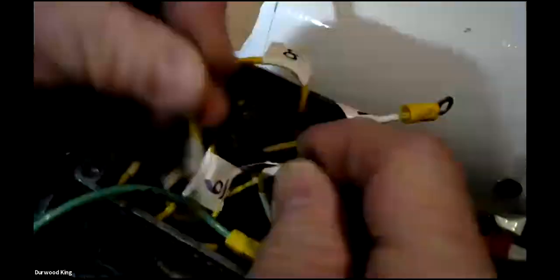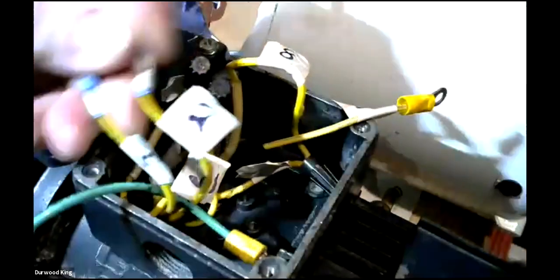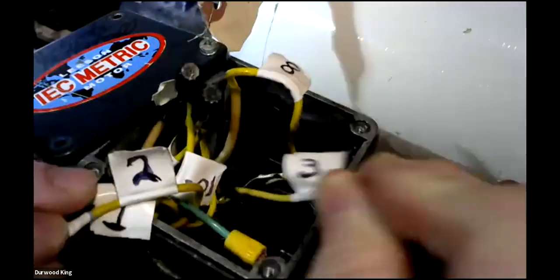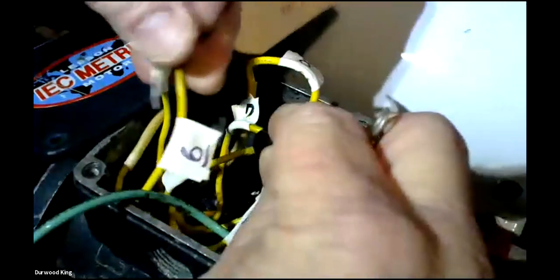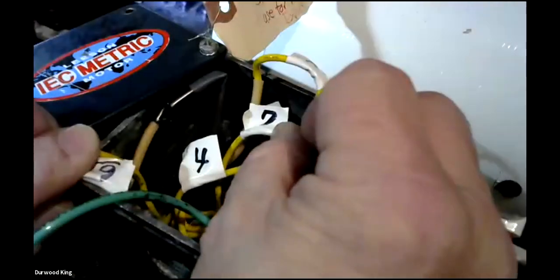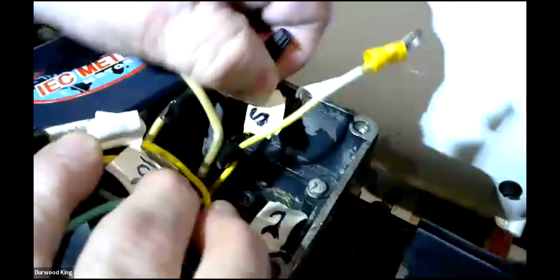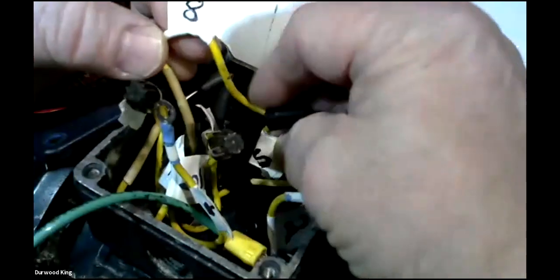And now just to show you, this is already hooked up, it's high voltage. You've got 1, 1 and 2, and you've got 3 that are available. Okay, down in there, you've got 6 and 9. Okay, you've got 4 and 7, 4 and 7 together. And then you have 8, and you've got 5. See that? So 8 and 5 are together down the wiring. There's your 5 and your 8. So it's configured for high voltage, and I've got a ground wire.